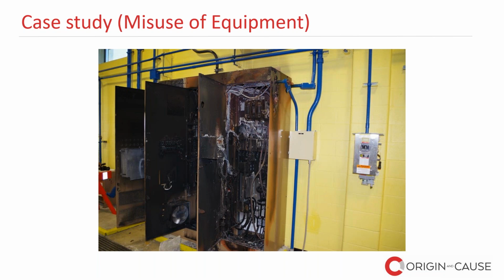And so further information provided determined that the VFD had not had any maintenance completed. This included thermal imaging to identify loose connections. So the combination of stressing the VFD under the greater than normal load and not completing any maintenance resulted in the failure of the device and caused the fire. Equipment should be operated and maintained as specified by the manufacturer.